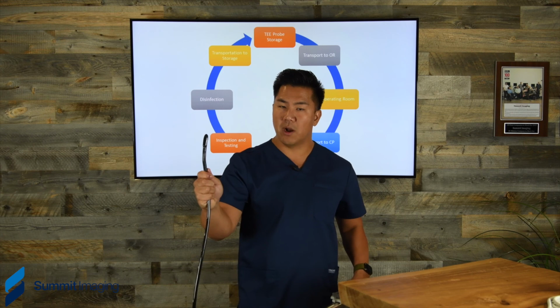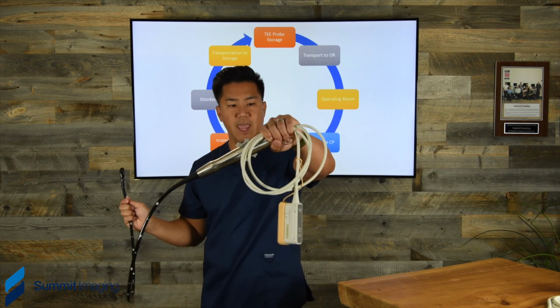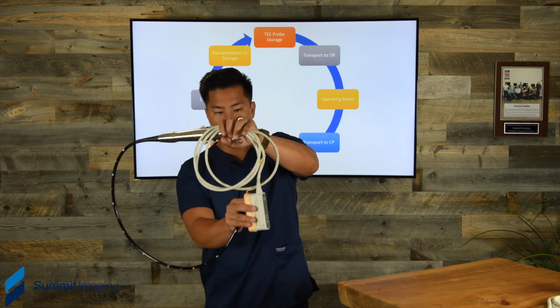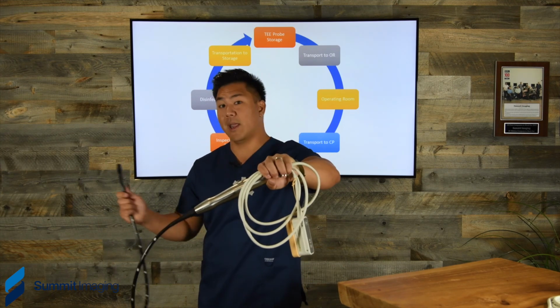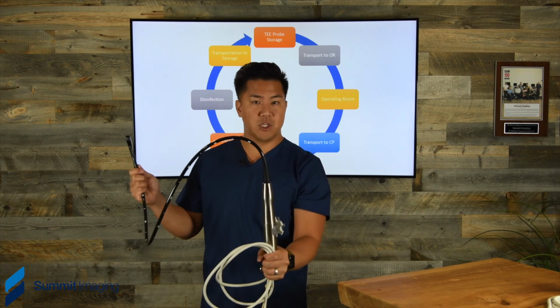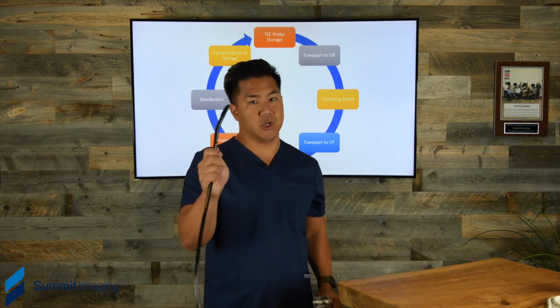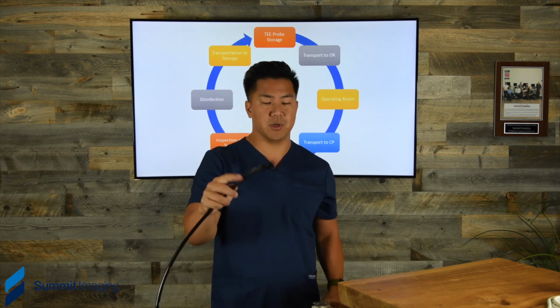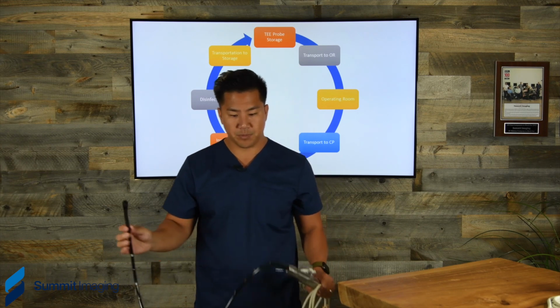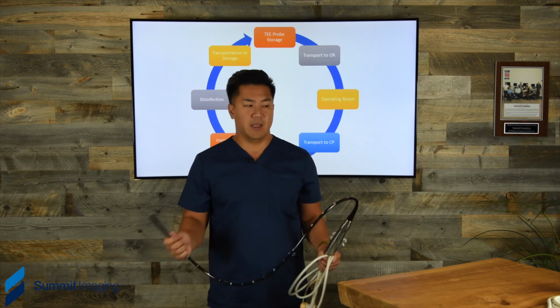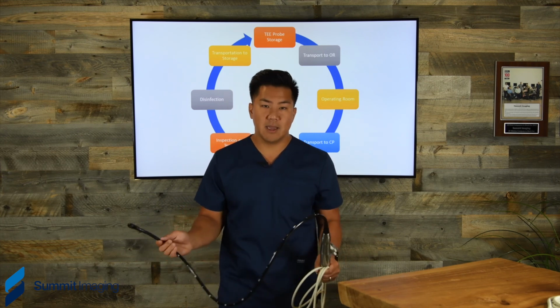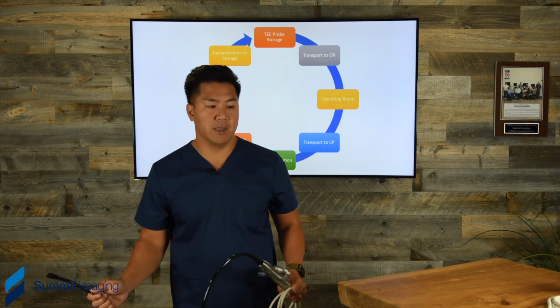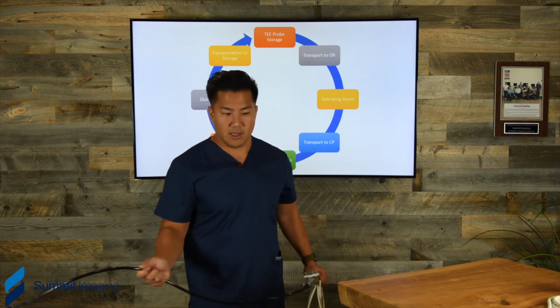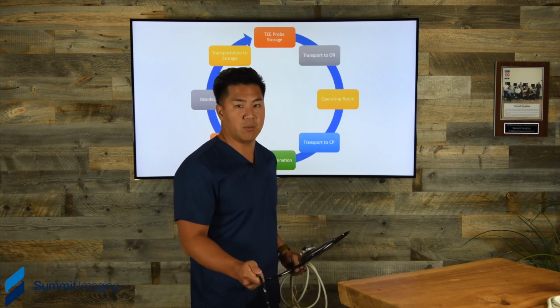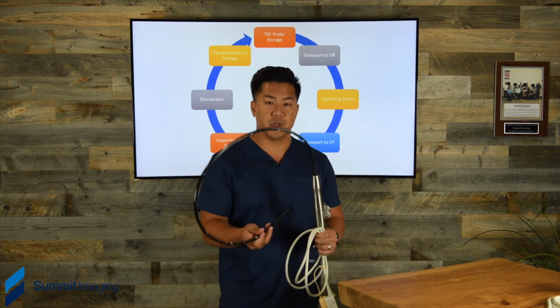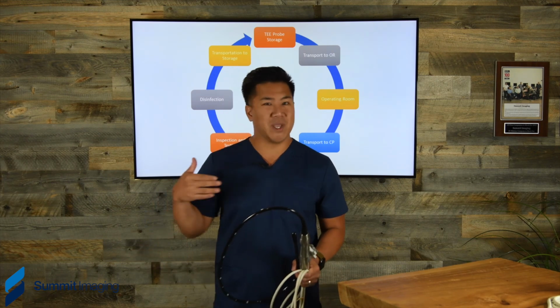So now you have full control of the tip of the transducer, you have control of the handle, and then this connector with a short leash here with your left hand or right hand will not swing around and bang things, especially keeping it away from the most sensitive part of the transducer, which is the TEE probe tip with the crystal on it. So we recommend carrying it in a way where you can control it with the idea that things aren't going to be swinging around unnecessarily, because if you carry it like this, you can risk banging it into a table. Another one is actually banging it into the side of doors as you're going in and out of rooms.